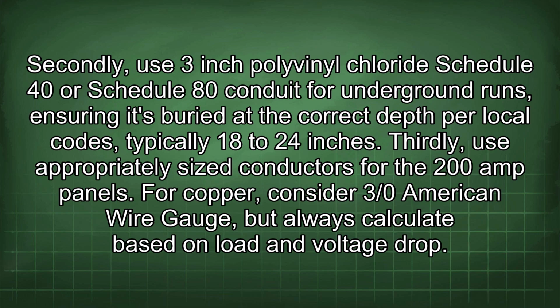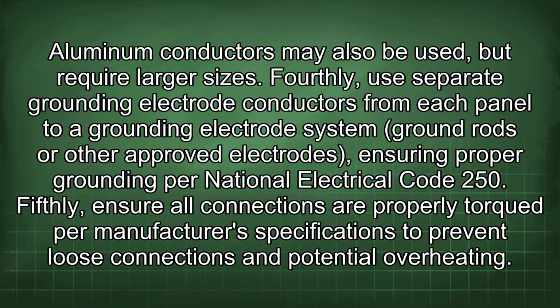Thirdly, use appropriately sized conductors for the 200 amp panels. For copper, consider 3/0 American wire gauge, but always calculate based on load and voltage drop. Aluminum conductors may also be used, but require larger sizes. Fourthly, use separate grounding electrode conductors from each panel to a grounding electrode system, ground rods, or other approved electrodes, ensuring proper grounding per National Electrical Code 250.